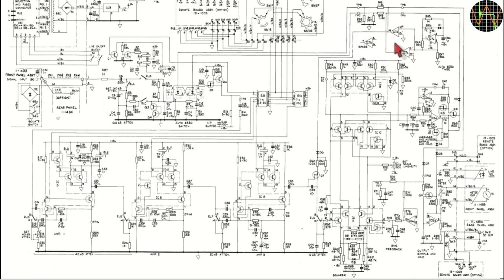One last remark on the schematics. There is a later model of the 9300 out there, the 9300B. It has a slightly different enclosure but exactly the same PCB and schematics. The only difference is that the tolerance of a few resistors have been improved from 1% to 0.1%. However, the specs of the two models are identical, so I suspect the tolerance changes are simply to make the calibration faster.